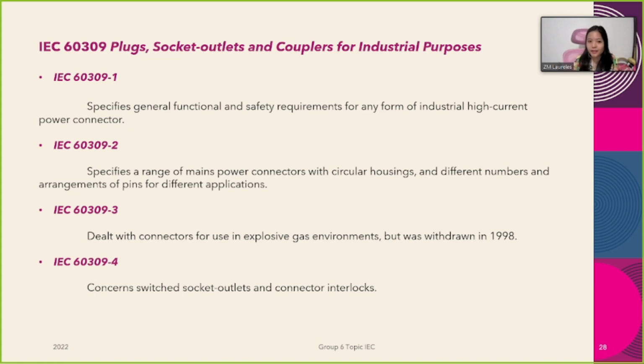Then, IEC 60309-2 specifies a range of mains power connectors with circular housings and different numbers and arrangement of pins for different applications. So, meron tayong mga connectors na pinoproduce in different variants. And kaya ganun yung pinoproduce natin so that meron tayong plug in this certain type na ginagamit lang din natin siya sa socket with the same type. And dahil doon, meron tayong iba't ibang current ratings such as 16 ampere, 32 ampere, 63 ampere, and then yung 125 na distinguished by different diameters of circular housings.